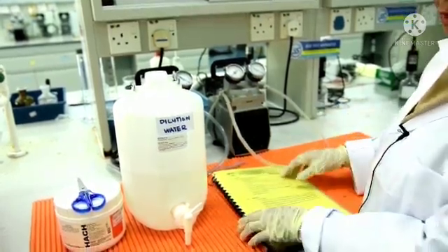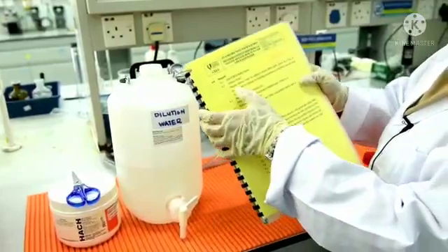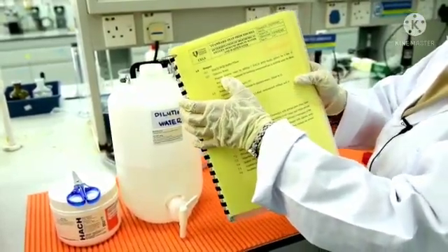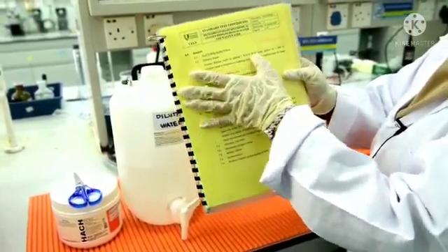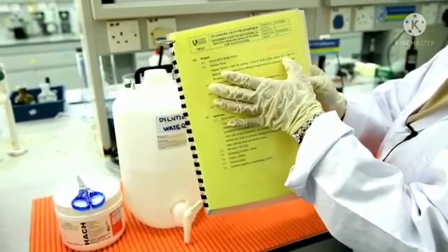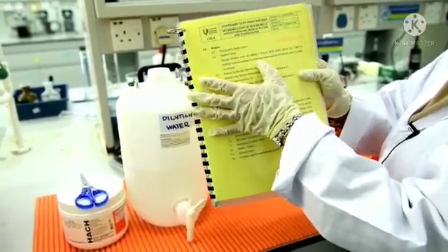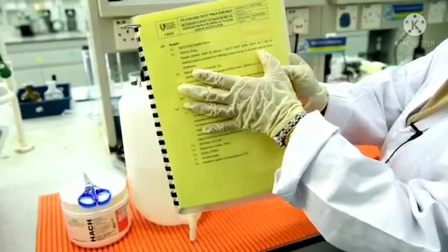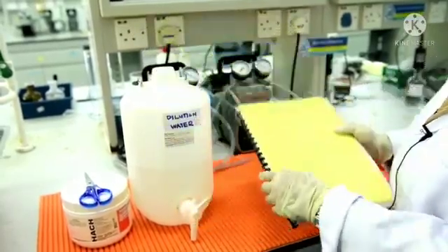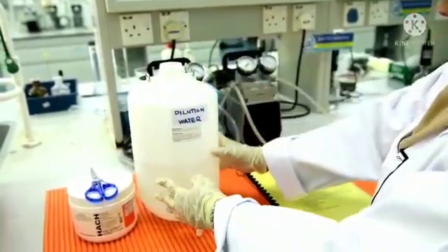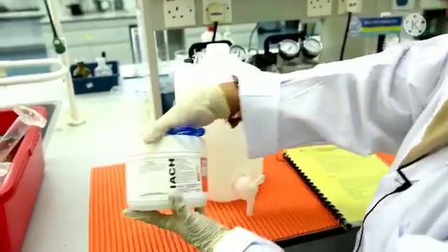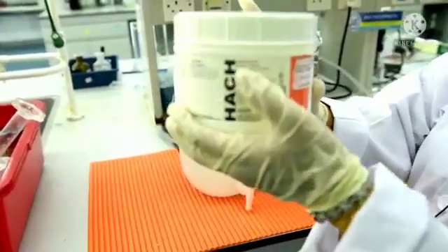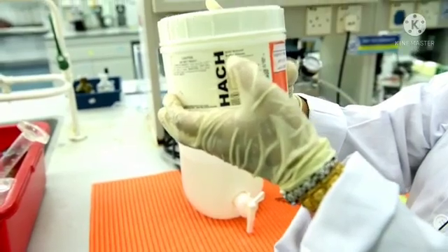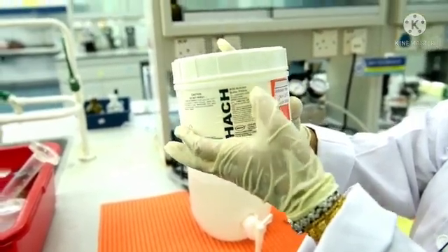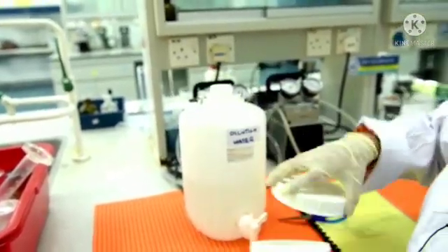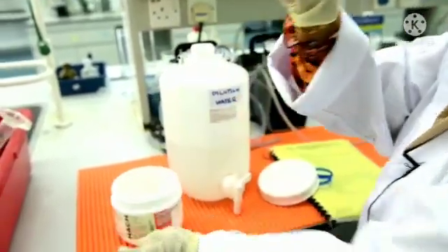Before we start, we must prepare dilution water first. So how to prepare dilution water? We must put 1 BOD buffer pillow for 3 liters in a container by bubbling compressed air in distilled water for about 30 minutes. So we must put 3 liters of distilled water. This is the BOD nutrient buffer pillow, and you must read here: for preparation of 3 liters of dilution water. That means we must put 3 liters with 1 buffer pillow.